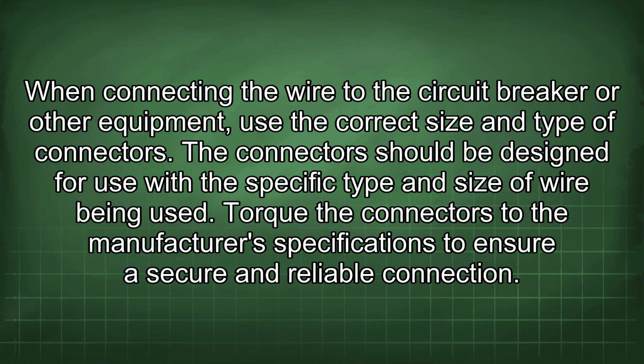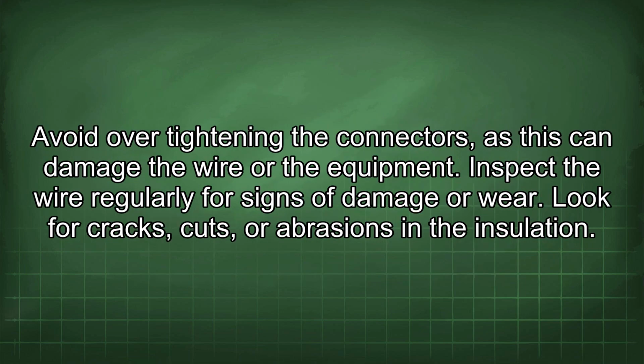When connecting the wire to the circuit breaker or other equipment, use the correct size and type of connectors. The connectors should be designed for use with the specific type and size of wire being used. Torque the connectors to the manufacturer's specifications to ensure secure and reliable connection. Avoid over-tightening the connectors, as this can damage the wire or the equipment.